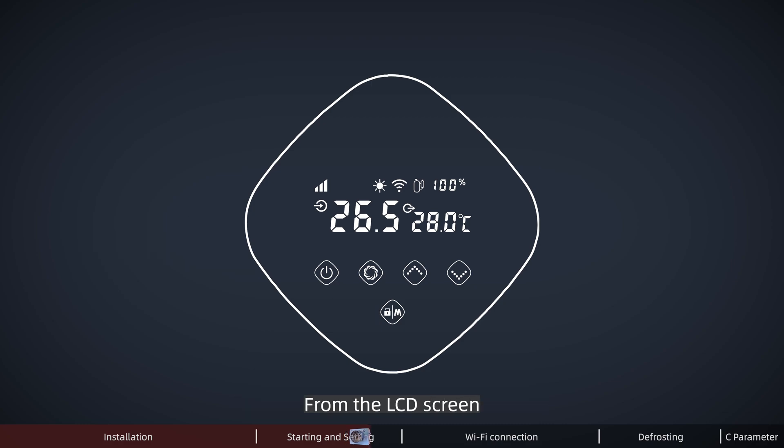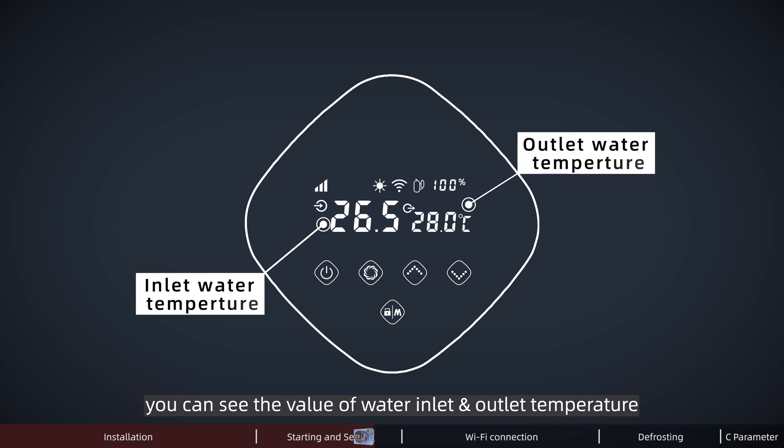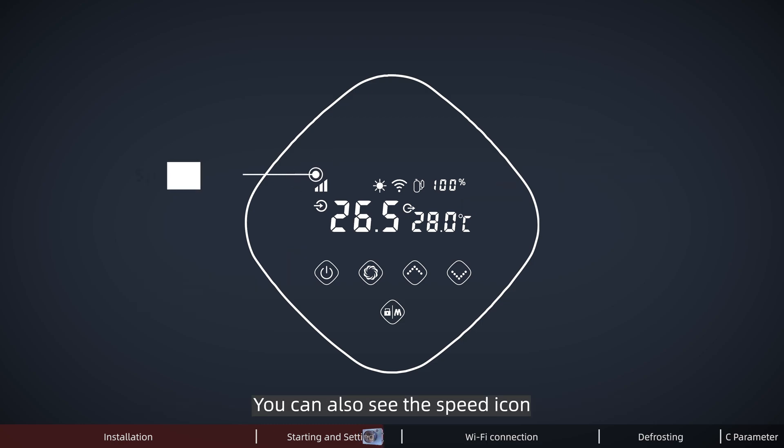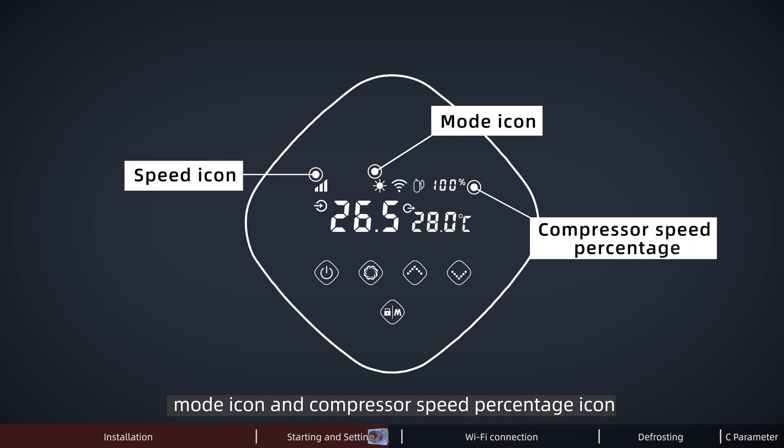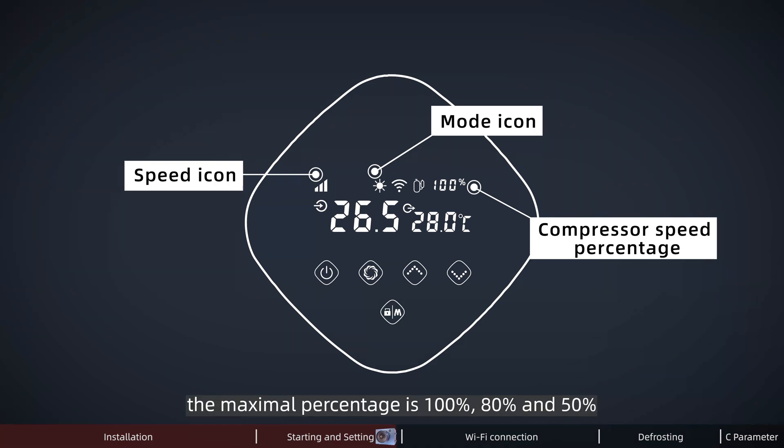From the LCD screen, you can see the value of water inlet and outlet temperature. Here, the inlet temperature is exactly the pool temperature. You can also see the speed icon, mode icon, and compressor speed percentage icon. From power mode, perfect mode to silent mode, the maximum percentage is 100%, 80%, and 50%.